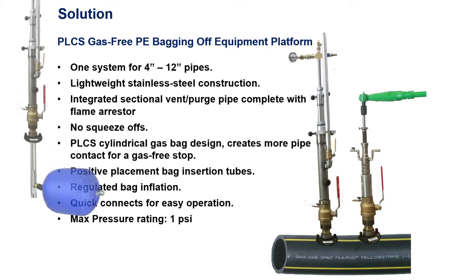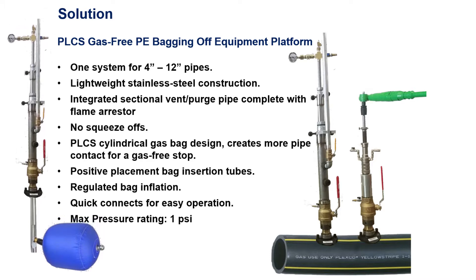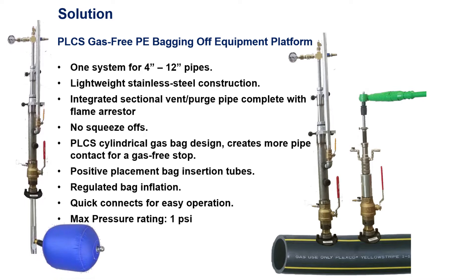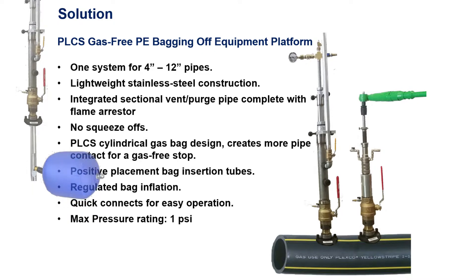The solution is to use the PLCS Gas-Free PE Bagging Off Equipment Platform for 4–12 inch pipes. Its lightweight stainless steel construction has an integrated sectional vent purge pipe complete with flame arrestor — so no squeezing off. The PLCS cylindrical gas bag design creates more pipe contact for a gas-free stop. Features include positive placement bag insertion tubes, regulated bag inflation, quick connects for easy operation, and a max pressure rating of 1 psi.